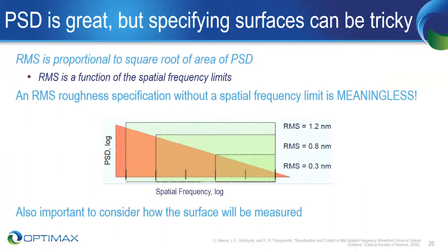It's really important to make sure that there's a commonly used algorithm for analyzing PSD. And then the other thing is it can be very difficult, as many technicians often don't necessarily think in Fourier space. They're used to looking at the optic, both in a false color surface image and looking at fringes, but then correlating that to what they need to do to be able to correct the surface.